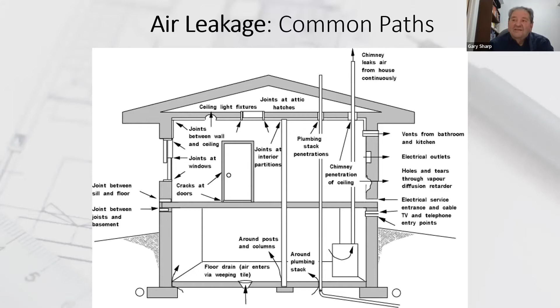So what we want to do with an air barrier is we want the air barrier to be continuous all the way around the building. The air barrier needs to connect to the windows, it needs to connect to the doors, it needs to connect to the concrete walls. And we're doing this to try and minimize the amount of unintentional air leakage through the house. And we do that by sealing all of the different components together. And we want it to be continuous. You should be able to see the red line there that goes all the way around the building. So a perfect air barrier would mean that the air changes on that house were 0. So that's the goal. Let's get to 0 and provide proper ventilation air to make the house nice and comfortable all the time.